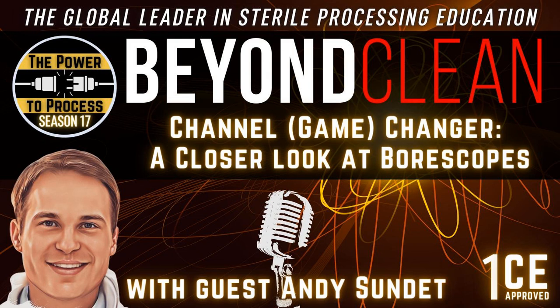Or think of it this way too. If you've got a workstation that's doing one colonoscope a year, you probably don't want to buy a super long borescope, because you're going to be dealing with that super long working length the whole time when you're only doing that once every once in a while. Think of the devices that you're going to be inspecting and the frequency that you're going to be inspecting those devices, and get the borescope that matches that from a diameter standpoint, as well as the length. You want to have enough length to get through stuff, but you don't want a jump rope at the workstation, bouncing all over the place.